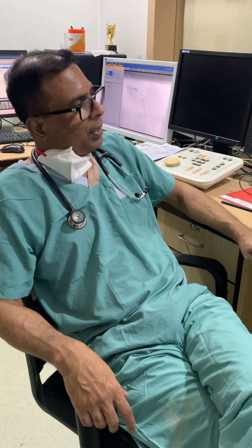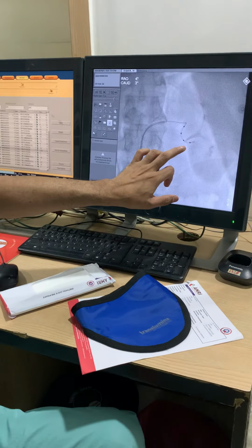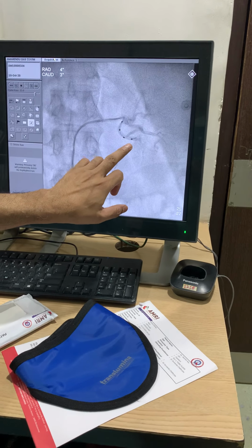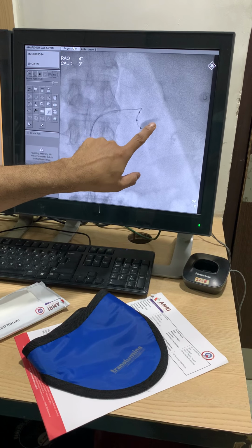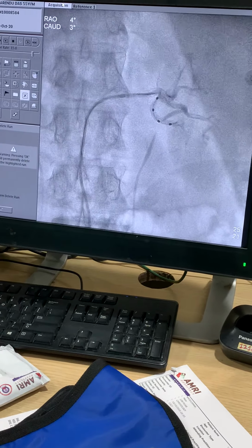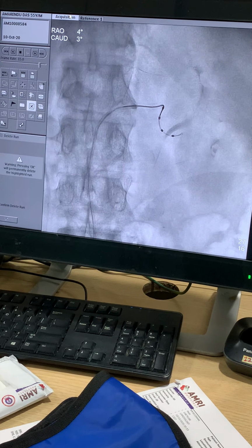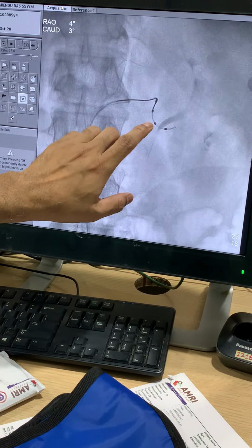Now this cooling is very important, and once you are satisfied, we ask the machine to give therapy to all four, 1, 2, 3, 4. So you select 1, 2, 3, 4 in the machine, and you must remember that this is the carina, and once you go into the other segment of the branch, this area should not be repeated. Once you have completed 60 seconds of therapy, and once you are happy with the position, then only start.